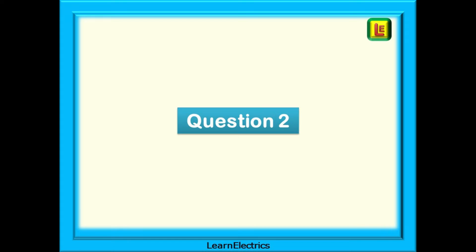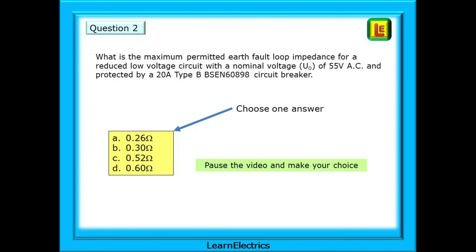Question 2 now, about reduced low voltage systems. This question is to do with 110 volt systems, as we would find on construction sites, for example. The 110 volt electrical supply is actually a 55, 0, 55 volt system. Let's look at the question. What is the maximum permitted earth fault loop impedance for a reduced low voltage circuit with a nominal voltage, U0, of 55 volts AC, and protected by a 20 amp type B, BS EN 60898 circuit breaker? Pause the video and make your choice, choosing just one answer from the four offered.